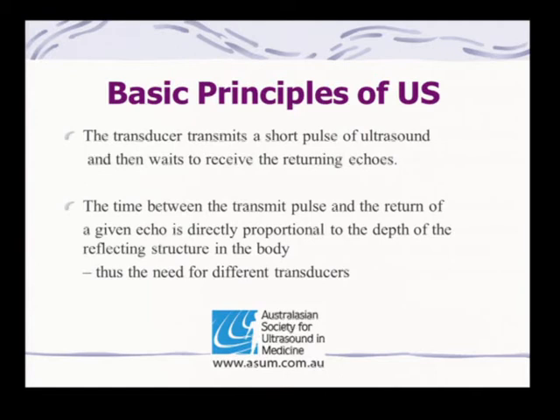So first of all, if you can just understand the basic principles of ultrasound: the transducer is going to emit a short pulse of ultrasound and then it waits to receive the returning echoes. And that time between leaving the transducer and the return is directly proportional to the depth of the reflecting structure in the body. So if you have a 150 kilogram woman, it might take a fair bit longer than a very thin lady. And thus the need for different transducers, our 2.5 megahertz as opposed to our 10 megahertz. So the lower the frequency, the deeper it's going to go into the body.